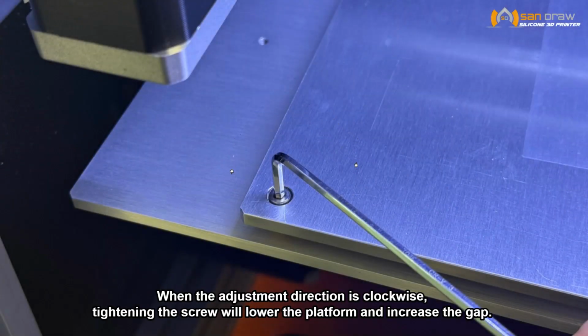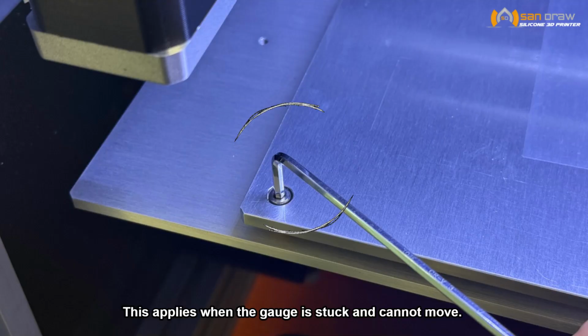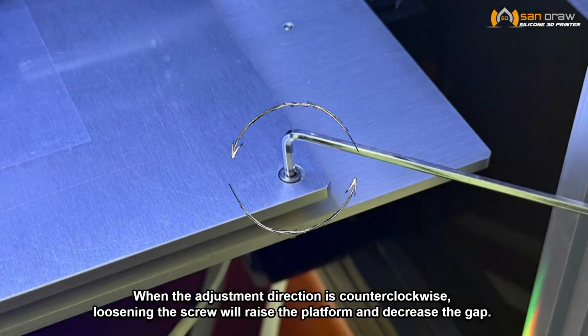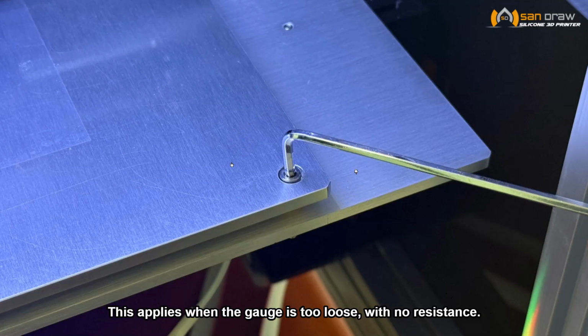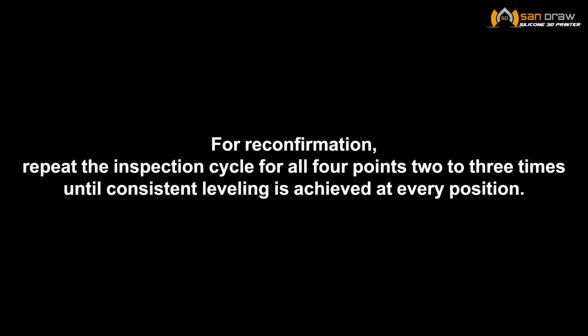When the adjustment direction is clockwise, tightening the screw will lower the platform and increase the gap. This applies when the gauge is stuck and cannot move. When the adjustment direction is counterclockwise, loosening the screw will raise the platform and decrease the gap. This applies when the gauge is too loose, with no resistance. For reconfirmation, repeat the inspection cycle for all 4 points 2 to 3 times until consistent leveling is achieved at every position.